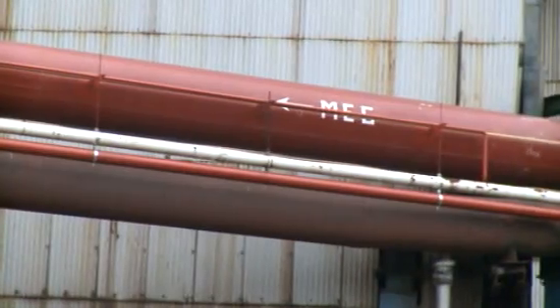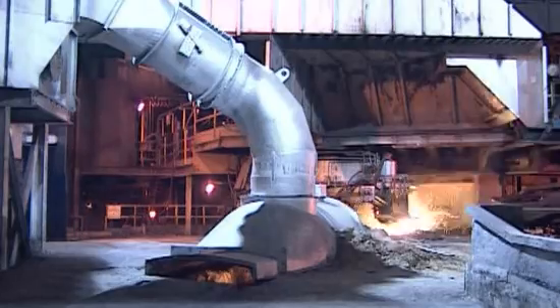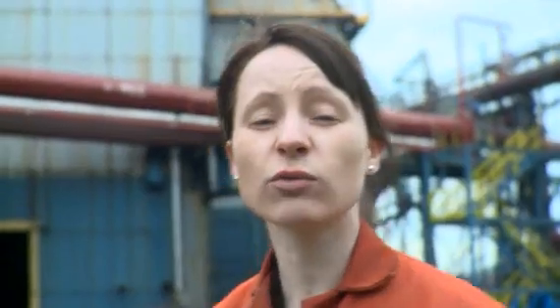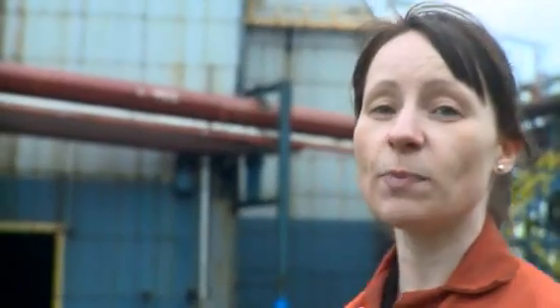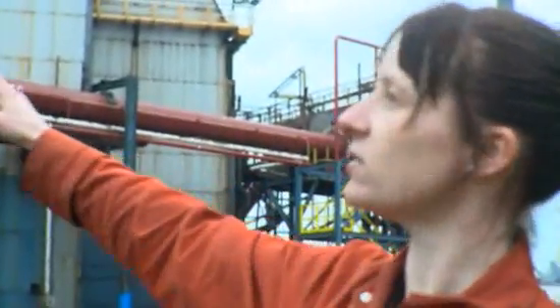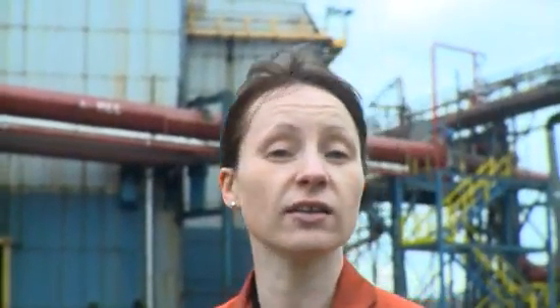Here at the plate mill is an example of some preventative maintenance that I was heavily involved in recently. If you look behind me you can see some main gas mains. This pipe provides coke oven gas to the furnace, so it provides the fuel to light the flares in the furnace itself. Basically it started to come to the end of its design life and was starting to show corrosion and other signs of wear, and it was also oversized for its current function. So rather than carry out patch repairs I decided to replace the main with this small 6 inch red pipe you can see following along here. This involved rehanging the new pipe and also rerouting services attached to the original main, because this main will be cut down, burnt up and recycled in the steel plant.